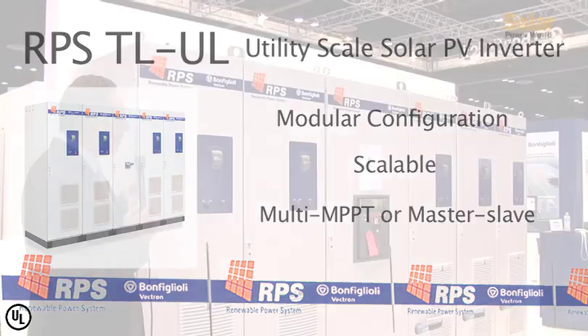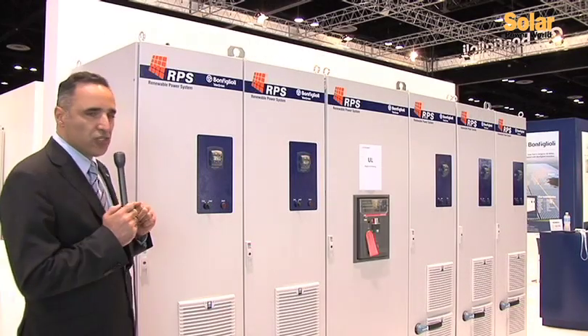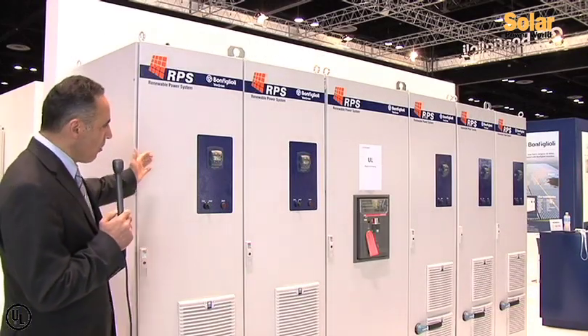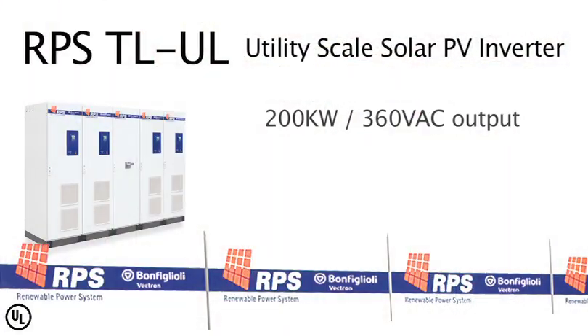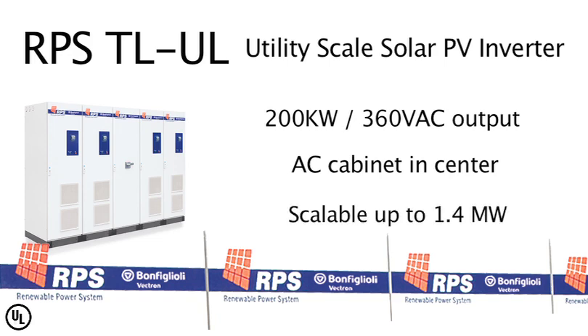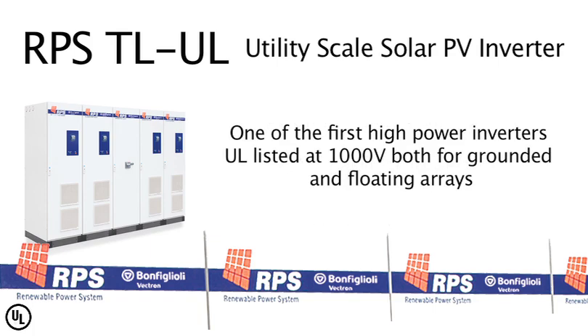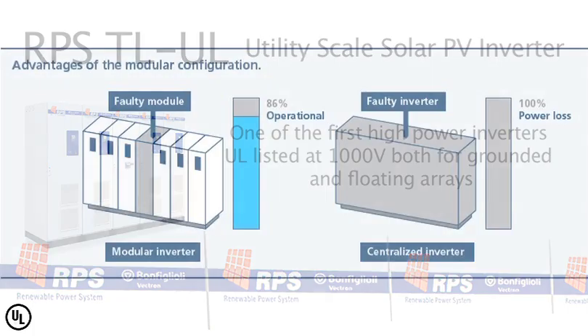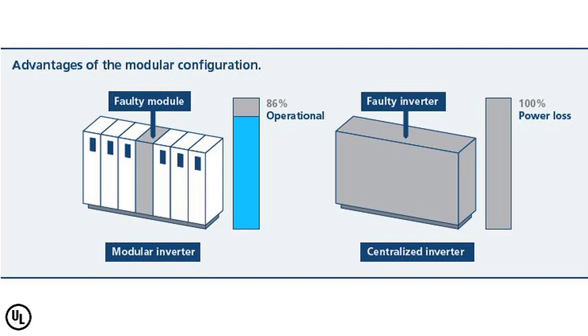What we're looking at here is a 1 megawatt modular inverter with 5 cabinets. Each cabinet is 200 kilowatts, and in the middle is the AC cabinet. Those are independent inverters, multi-MPPT, scalable, and flexible in the field. So by having independent multi-MPPT, if one inverter module or cabinet goes down, the rest of the modules will still be operable.